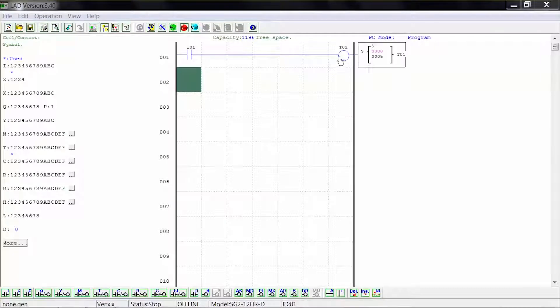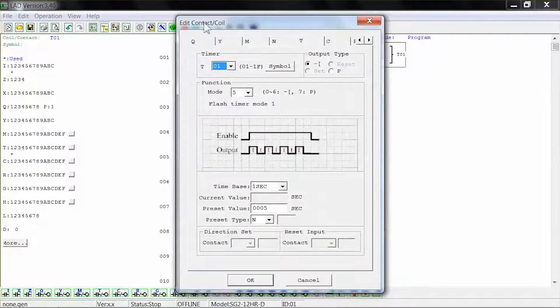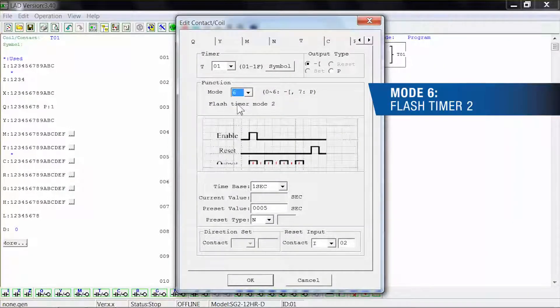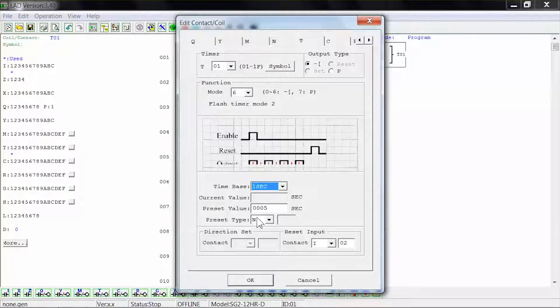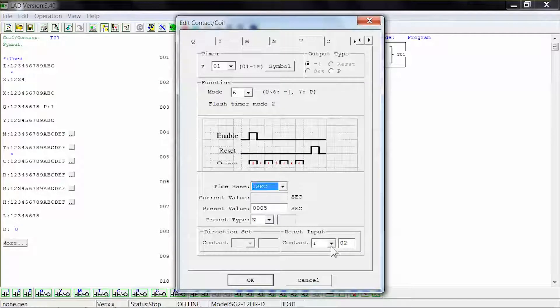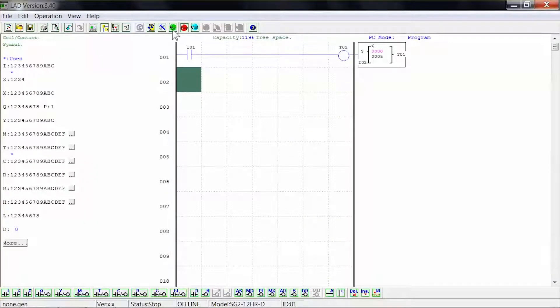For the next example, double-click the timing coil to bring up the edit coil window. Select function mode number 6, which is a flash timer version 2. Select the time base for 1 second, the preset value for 5 seconds shown as 0005, and the preset type to be N for numeric constant. Select the reset input to be contact I02. Click OK to close the window and click run to start the simulation.